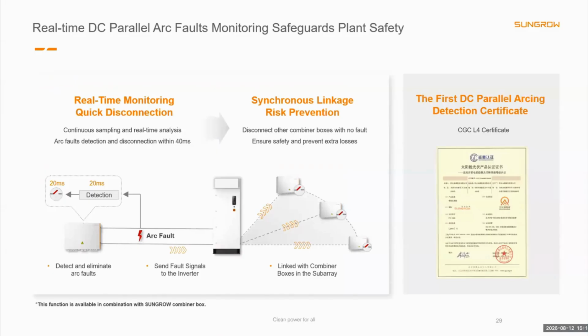Our 1 plus X system continuously monitors the DC side for parallel arc faults. When a fault is detected, it can respond and disconnect within approximately only 40 milliseconds. The inverter can also coordinate with Sungrow smart combiner boxes to isolate the risk across the subarray. This can provide fast and intelligent fault protection.